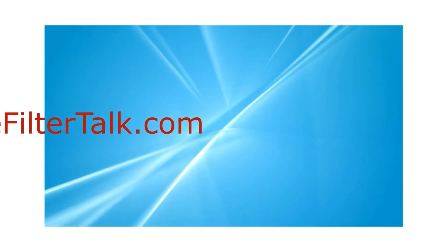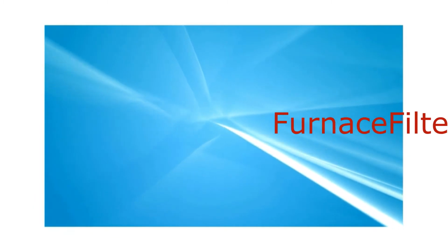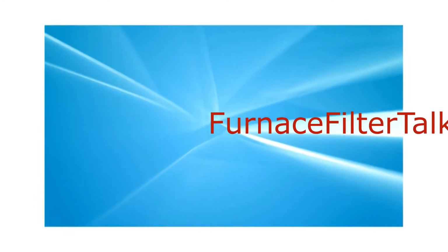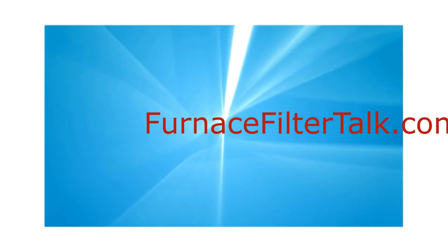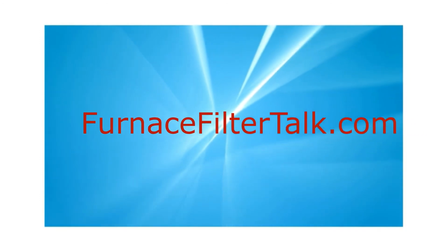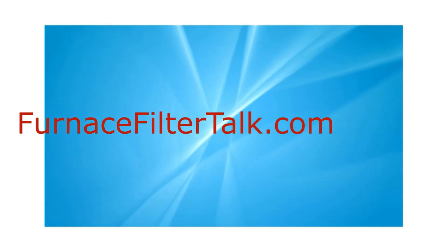Most systems can handle up to MERV 13 with no issues, as filter technology has made the higher MERVs, up to 13, work in most scenarios, resulting in filters with new filter media technology and new pleating technology. So as you can see, higher MERV-rated filters are engineered not to be too restrictive, so you don't have to worry about the filter causing you any issues when it is new and used correctly.